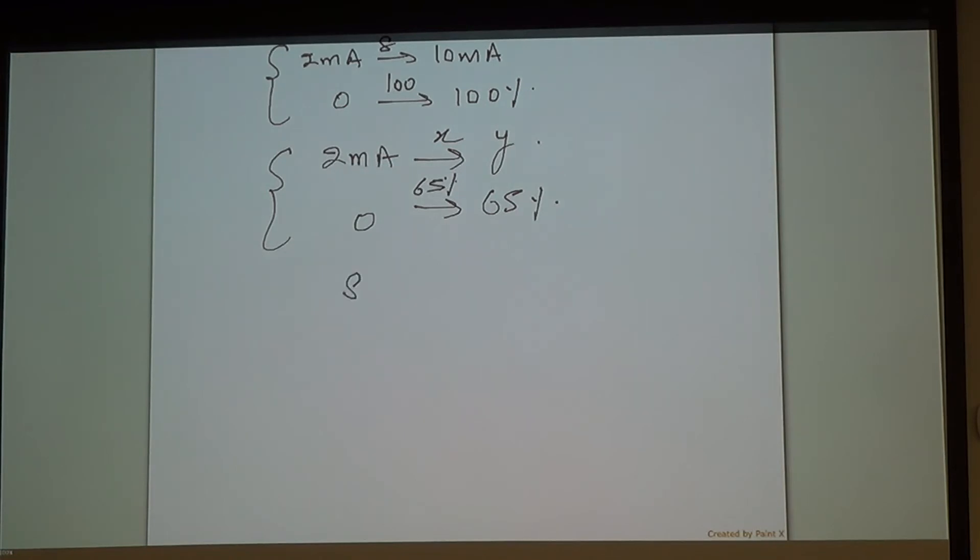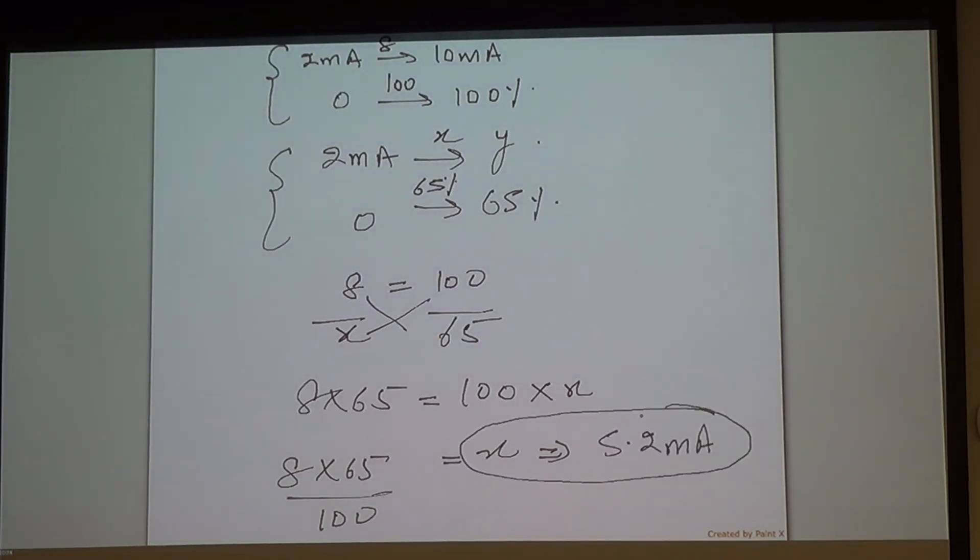Let's go put the numbers in. 8 brings the change of 100, X will bring the change of 65. Ratio proportion. Let's cross multiply. 8 times 65 is equal to 100 times X. What is my X equal to? 8 times 65 over 100. Please do the math for me. Give me my answer. 5.2 milliamps.